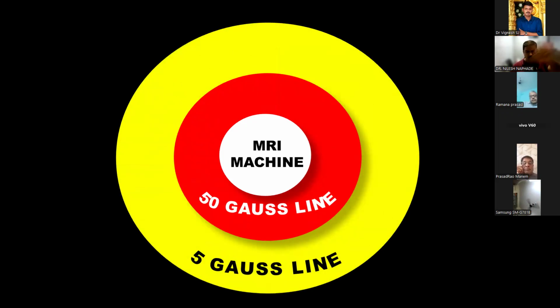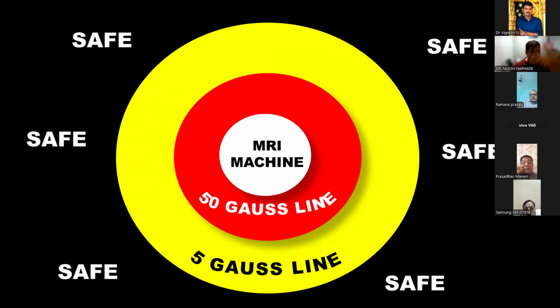And the outer border of the yellow circle is the 5 Gauss line, so outside that yellow outline, everything is safe. That is the safe area for a pacemaker, for any other equipment. That outer border is called the pacemaker safety line. So always, if you have a pacemaker or you know that a patient's attendant has a pacemaker, he should be standing outside the 5 Gauss line.